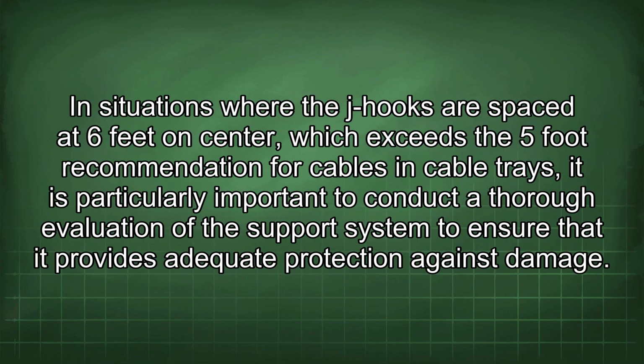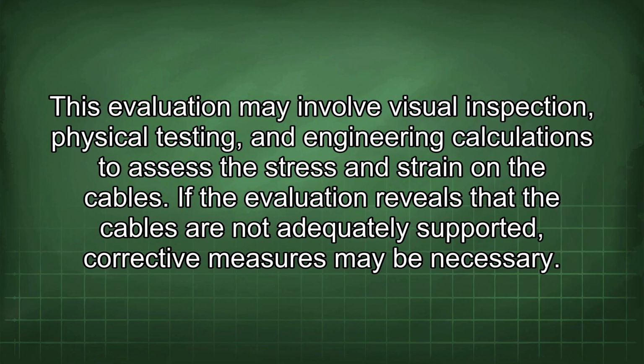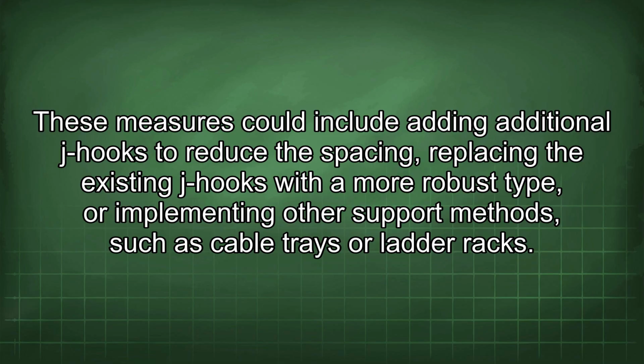In situations where the J-hooks are spaced at 6 feet on center, which exceeds the 5-foot recommendation for cables in cable trays, it is particularly important to conduct a thorough evaluation of the support system to ensure that it provides adequate protection against damage. This evaluation may involve visual inspection, physical testing, and engineering calculations to assess the stress and strain on the cables. If the evaluation reveals that the cables are not adequately supported, corrective measures may be necessary. These measures could include adding additional J-hooks to reduce the spacing, replacing the existing J-hooks with a more robust type, or implementing other support methods, such as cable trays or ladder racks.